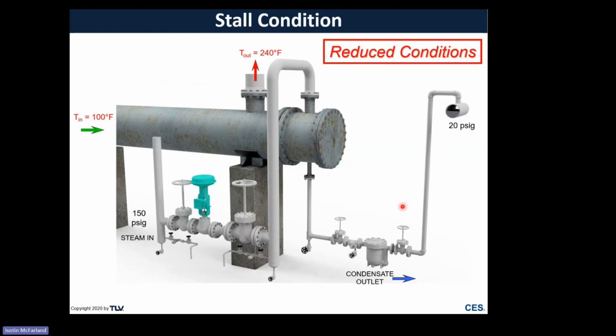Now we've got a reduced condition scenario, or a turn down scenario. Our product flow rate drops even further, steam flow rate drops even further. And now we're in a scenario where we've got -9 psig differential pressure. So because that's negative differential, the steam trap is not going to work.